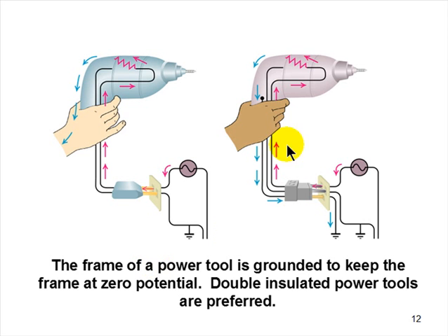The idea, why do you ground any motor, any power tool, is to keep the housing at 0 potential. This housing is at 0 potential. Nothing's going to move out of that housing to a ground. This one wasn't. The potential here was 115 volts through your body to ground. You became part of the circuit. If you can keep this housing at 0 potential, what if you took your voltmeter and plugged it into a receptacle in your house and you read 0 volts? You got 0 potential to do work. As long as you can read from this housing to ground is 0, you're safe. If you read a voltage from this housing to ground, you're in trouble. And the higher that reading is, the more death-defying that becomes.